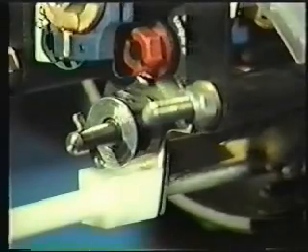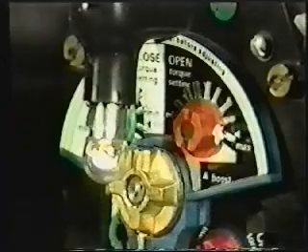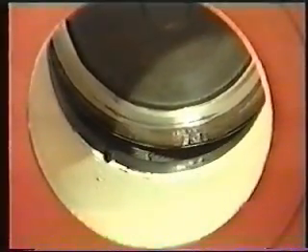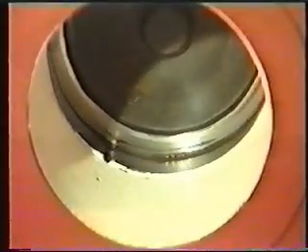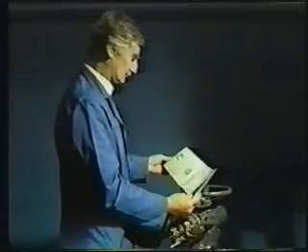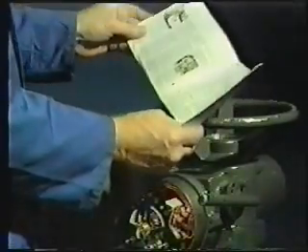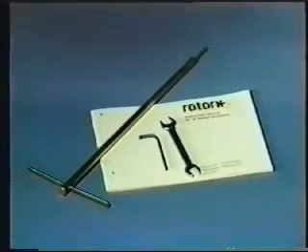It switches itself off at either end of valve travel, either by sensing it has moved the valve's closing mechanism far enough, or by feeling that the valve is tightly closed. However, careful setting of this switch mechanism is essential to the efficient operation of the valve on which it is mounted. As we shall see, this is not difficult, and these are all the tools you need.